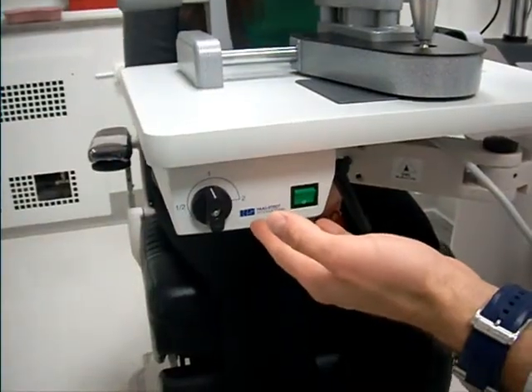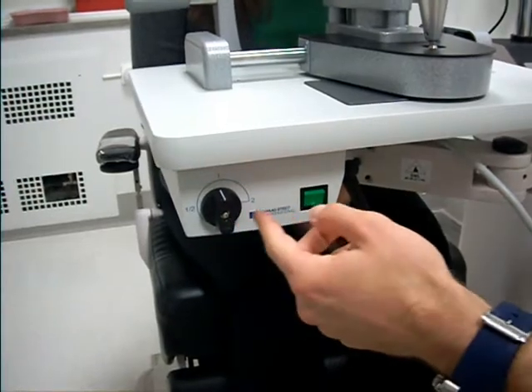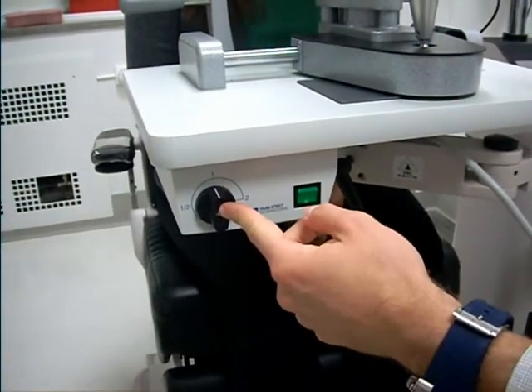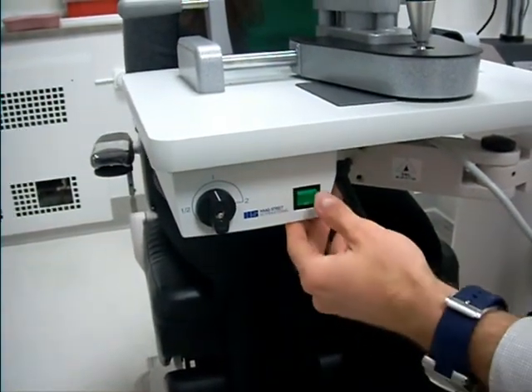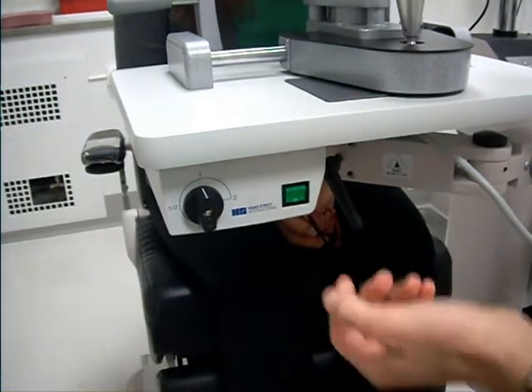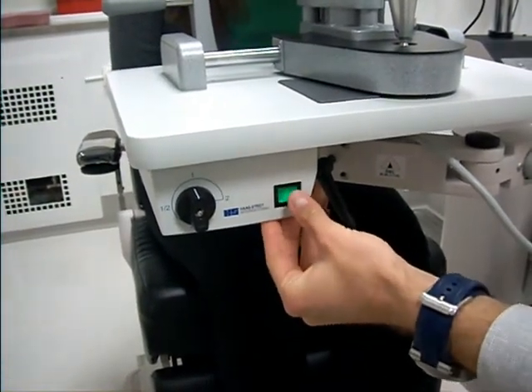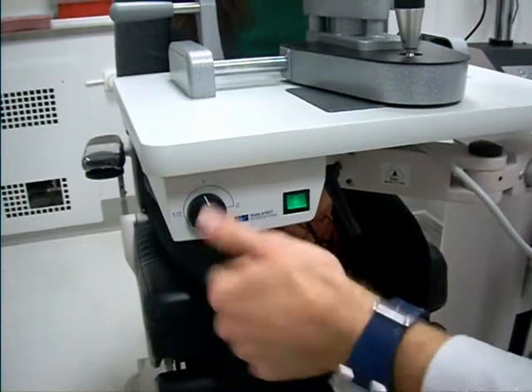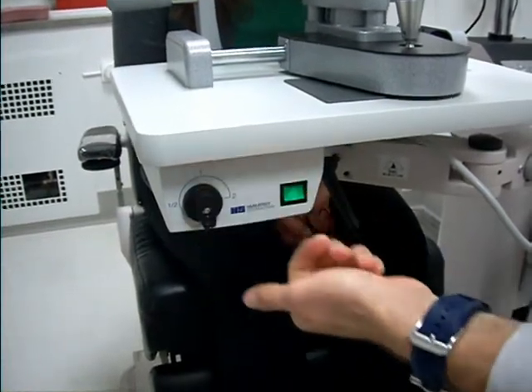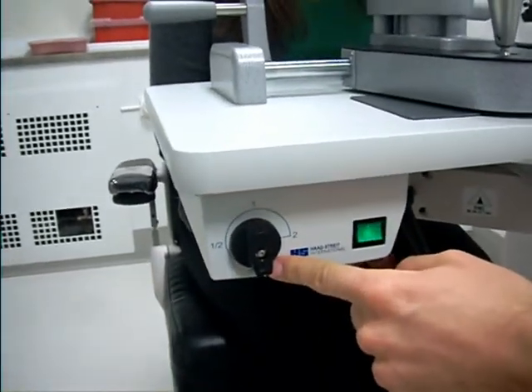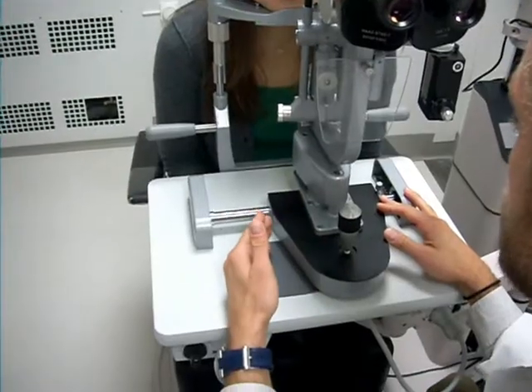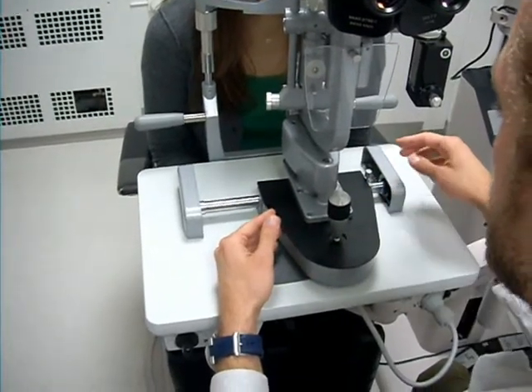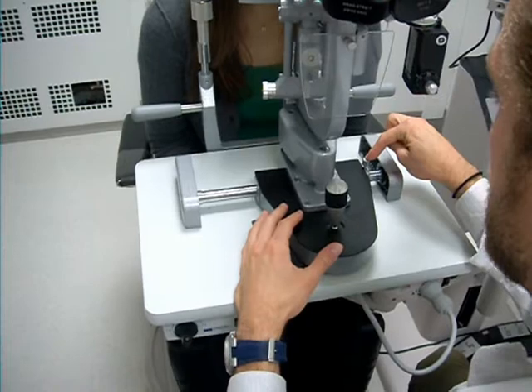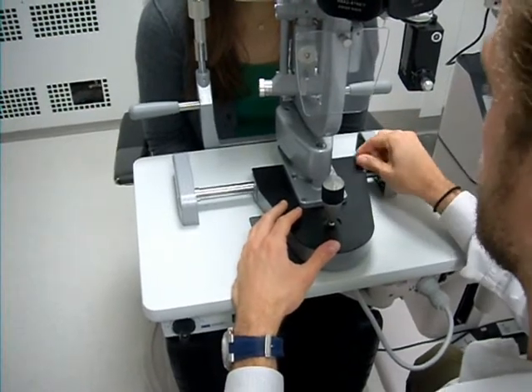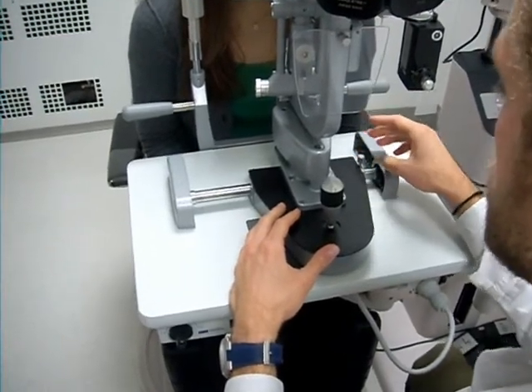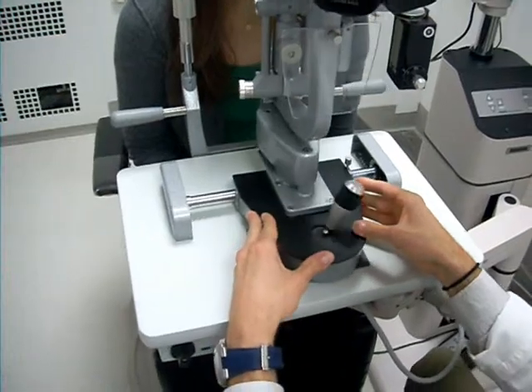Just below the stand of the machine, we have the power and light intensity knobs. So the first thing you want to do after you get the eyepieces aligned, you want to flip on the switch, but before you do so, you want to make sure that the power is on this lowest setting, just to make sure you don't blind the patient. When you first start using the machine, it should be in a locked position. So this knob is the locking mechanism. So you want to turn this counterclockwise to unlock the machine, and you'll be able to freely move the base of the machine.